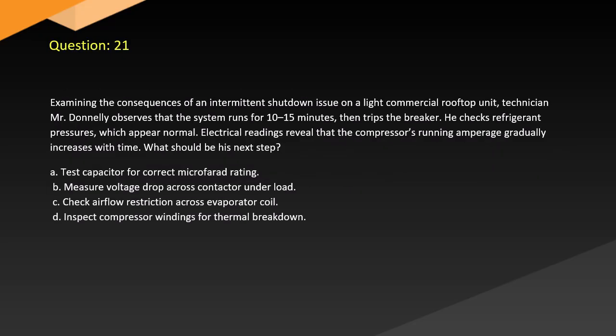Question 21. Examining the consequences of an intermittent shutdown issue on a light commercial rooftop unit, technician Mr. Donnelly observes that the system runs for 10 to 15 minutes, then trips the breaker. He checks refrigerant pressures, which appear normal. Electrical readings reveal that the compressor's running amperage gradually increases with time. What should be his next step? A. Test capacitor for correct microfarad rating. B. Measure voltage drop across contactor under load. C. Check airflow restriction across evaporator coil. D. Inspect compressor windings for thermal breakdown.